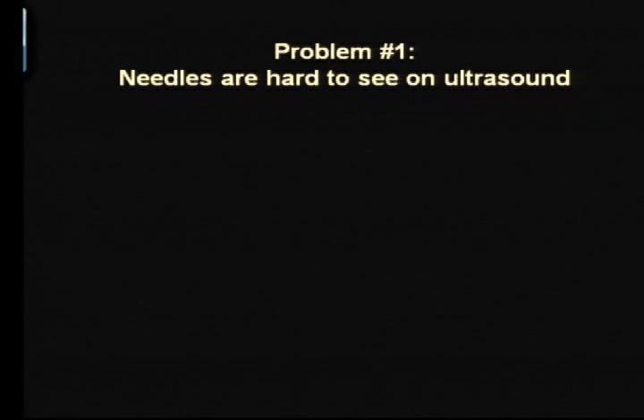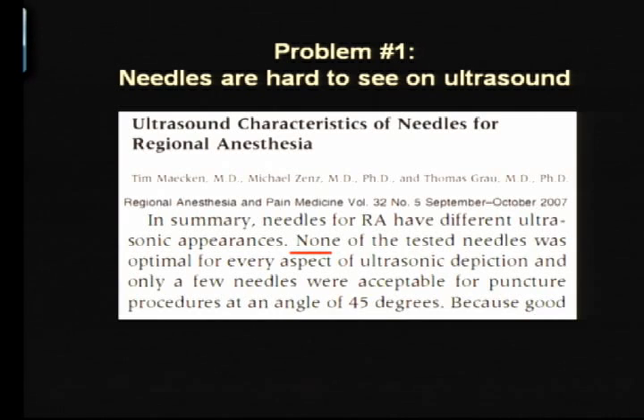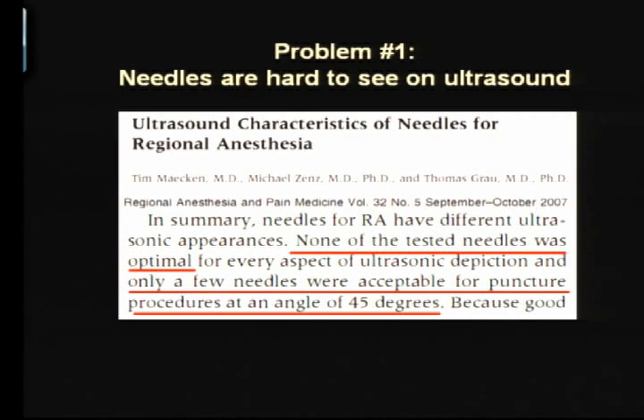And the first problem arises from the fact that needles are actually very hard to see in ultrasound. Most of the standard block needles behave as specular reflectors, and so the ultrasound waves reflect away from the probe rather than back to it. And in 2007, Thomas Grau and his colleagues demonstrated this when they tested all the available block needles and found that none of them was optimal, and certainly at angles more than 45 degrees, very, very few of them produce an acceptable image. We're not even talking about a good image, an acceptable image.